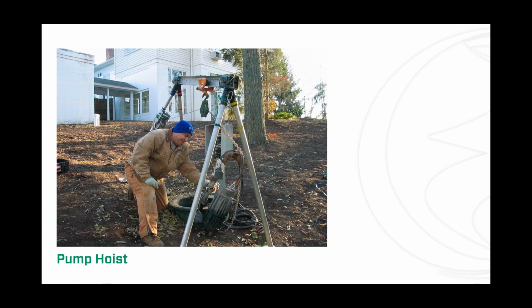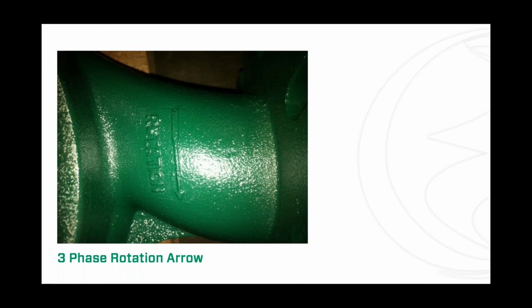Work smart. Another troubleshooting tip: if you have a three-phase pump, it can be wired to rotate in the wrong direction, so make sure you check that your pump is in the correct rotation. At Zoeller, we try to make that simple - on the volute of this particular pump, we have the word 'rotation' with an arrow pointing in the correct direction the impeller should spin. It's very important that this is checked.